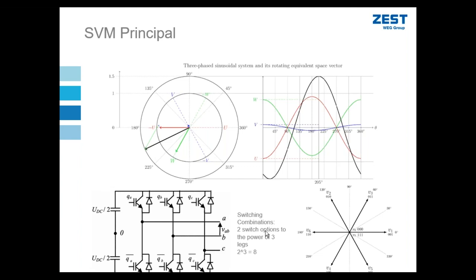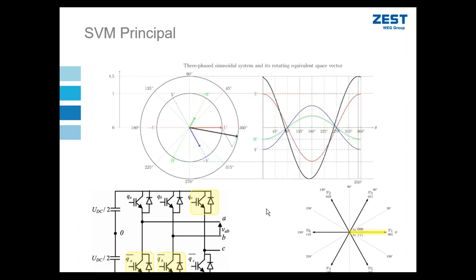So just to establish how many switching combinations are possible from a standard low voltage VSD with six IGBTs in the inverter section. Well, we have two switches and we have three legs. So simple mathematics means that we go 2^3. That gives us 8 possible switching vectors that we can achieve from this scenario. Those 8 vectors are shown on the right, bottom right. We can have V1, V3, V2, V6, V4, and V5. So that is 6 vectors, and then we have 2 zero vector possibilities. So let's maybe make this a little bit more practical.